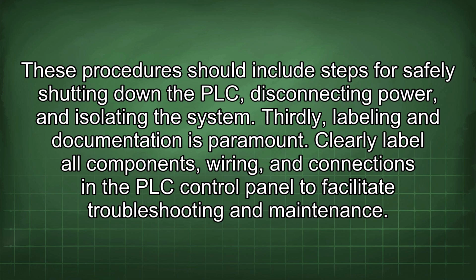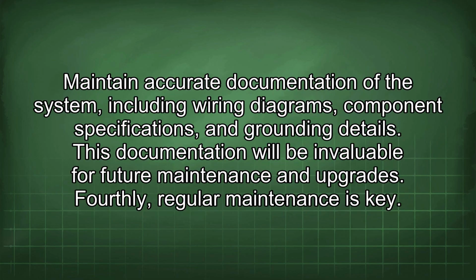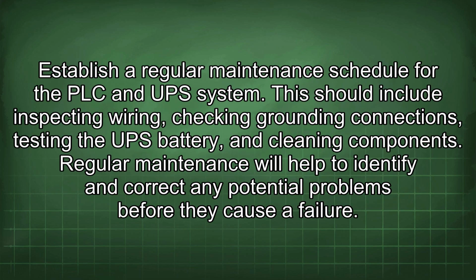Thirdly, labeling and documentation is paramount. Clearly label all components, wiring, and connections in the PLC control panel to facilitate troubleshooting and maintenance. Maintain accurate documentation of the system, including wiring diagrams, component specifications, and grounding details. This documentation will be invaluable for future maintenance and upgrades. Fourthly, regular maintenance is key. Establish a regular maintenance schedule for the PLC and UPS system. This should include inspecting wiring, checking grounding connections, testing the UPS battery, and cleaning components. Regular maintenance will help to identify and correct any potential problems before they cause a failure.